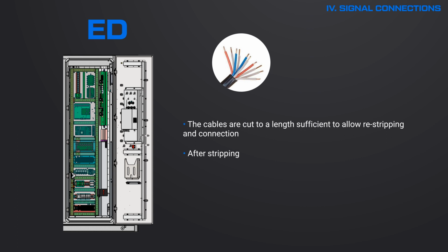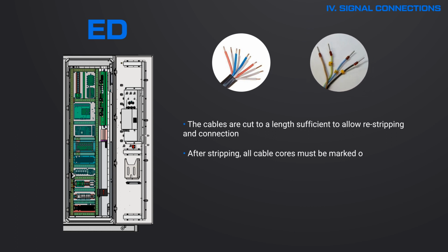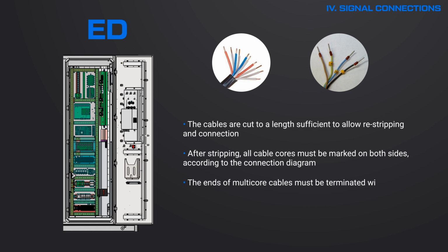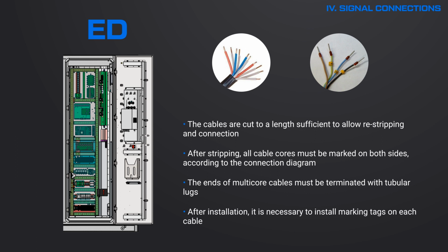After stripping, all cable cores must be marked on both sides, according to the connection diagram. The ends of multi-core cables must be terminated with tubular lugs. After installation, it is necessary to install marking tags on each cable on both sides according to the connection diagram.